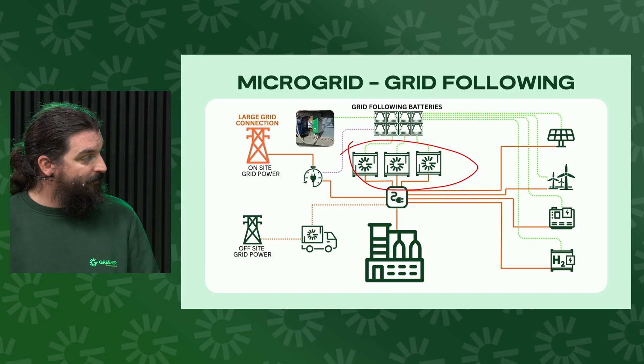That's the droop control, because if you follow the voltage over a line, the voltage is dependent on the loss over that line - there's impedance and resistance that has an influence on that. But the frequency throughout a grid is the same regardless of distance, it cannot change. So if there's a large problem in Spain, they would know in the Nordics within a few microseconds, because they would see a bump in the frequency, and all the other things would start to adjust immediately.